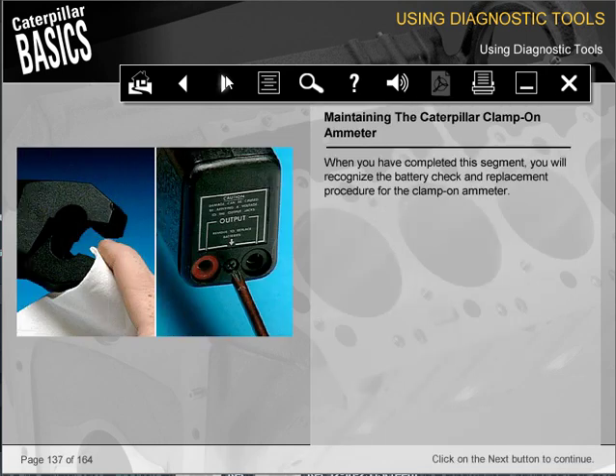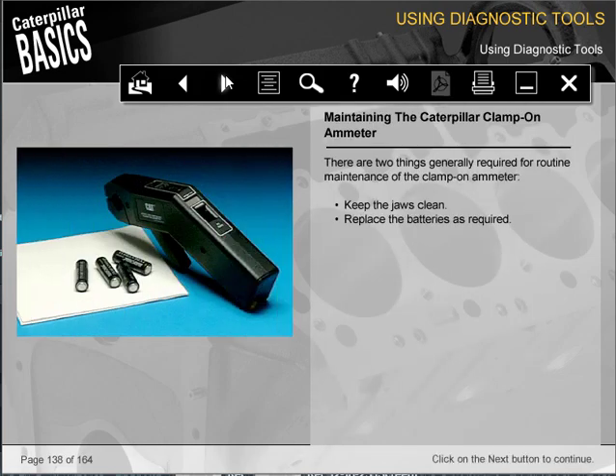When you have completed this segment, you will recognize the battery check and replacement procedure for the clamp-on ammeter. There are 2 things generally required for routine maintenance of the clamp-on ammeter. Keep the jaws clean. Replace the batteries as required.